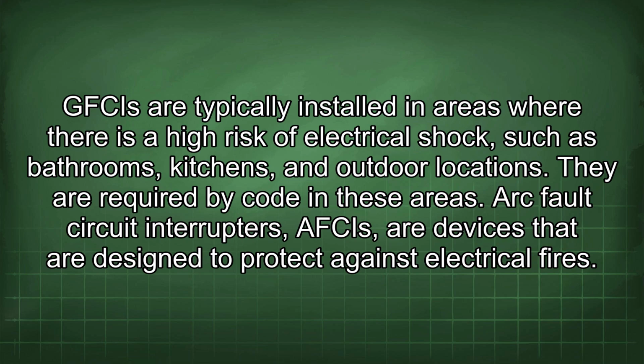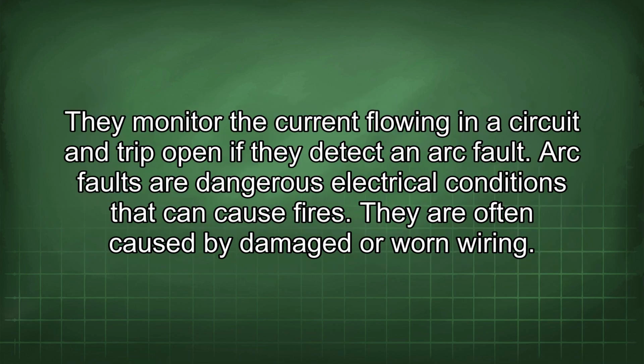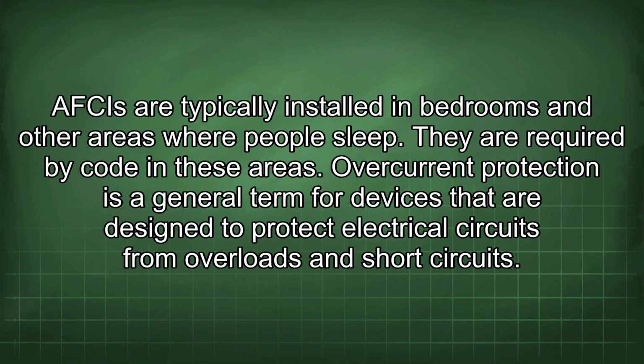Arc fault circuit interrupters, AFCIs, are devices that are designed to protect against electrical fires. They monitor the current flowing in a circuit and trip open if they detect an arc fault. Arc faults are dangerous electrical conditions that can cause fires. They are often caused by damaged or worn wiring. AFCIs are typically installed in bedrooms and other areas where people sleep. They are required by code in these areas.